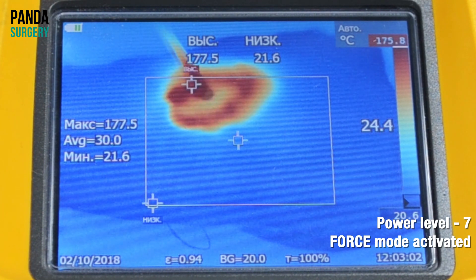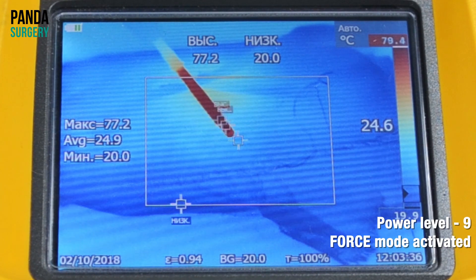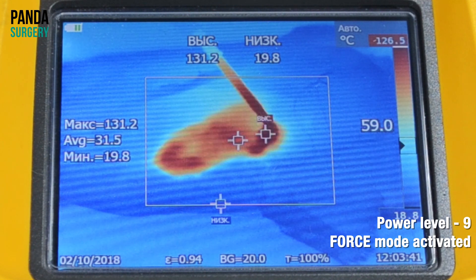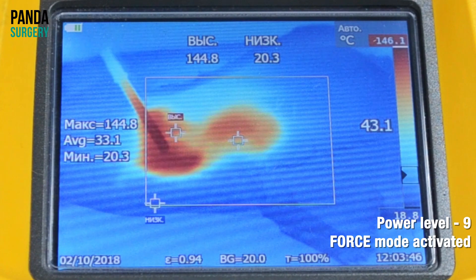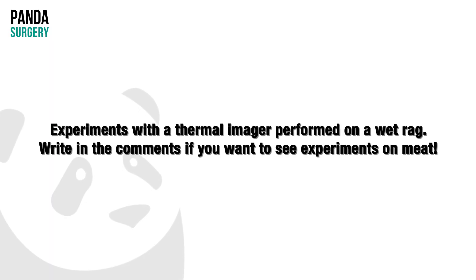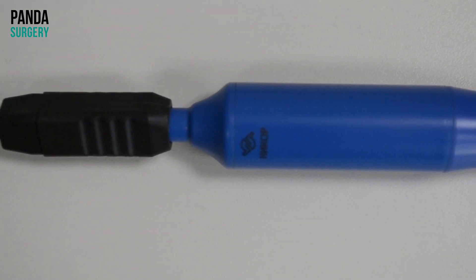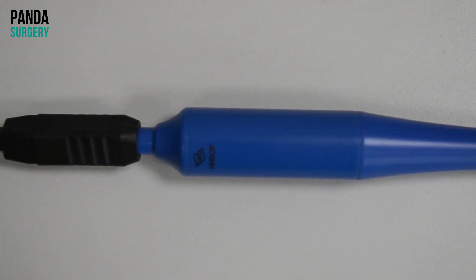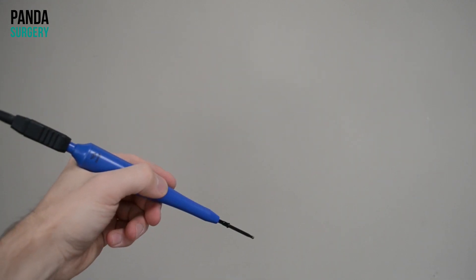The source of EMI field is located in the operating room far from other equipment. It is safe enough for the patient due to the short time of power activation needed to stop a bleeding. These effects lead to a better level of electromagnetic environment during the activation of the spray mode in your operating room. There is no influence on patient's monitors, displays, and other equipment during activation of Nikkor spray plasma. The compactness of the solution will allow you to easily add the equipment into the equipment trolley which you already have.